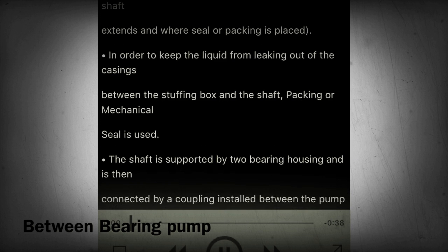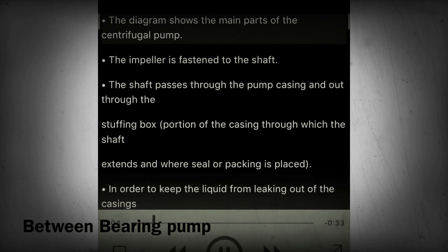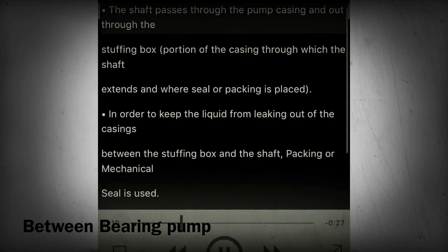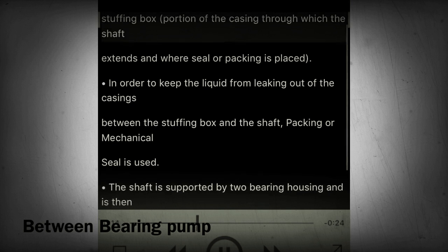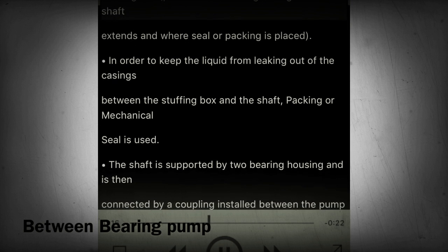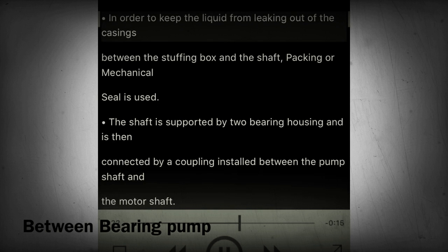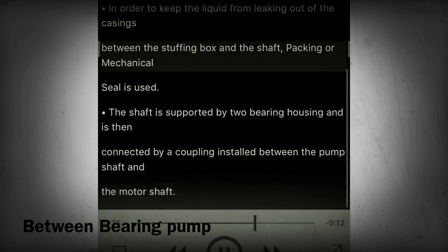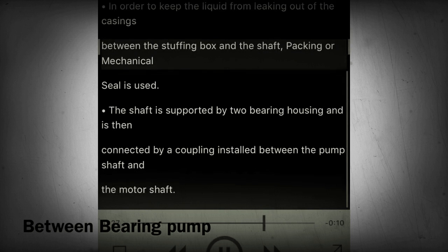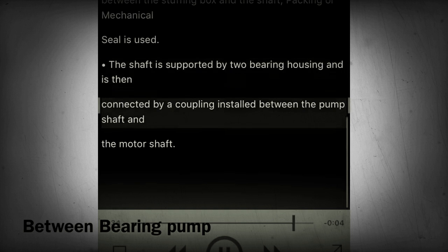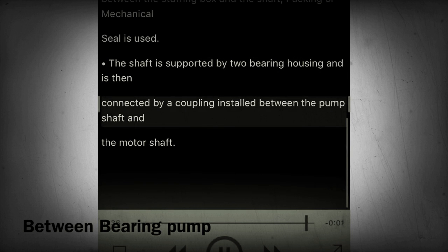Sections 18-19 - Nomenclature and Description. The diagram shows the main parts of the centrifugal pump. The impeller is fastened to the shaft. The shaft passes through the pump casing and out through the stuffing box — the portion of the casing through which the shaft extends, where a seal or packing is placed in order to keep the liquid from leaking out of the casing. Packing or mechanical seal is used. The shaft is supported by two bearing housings and is connected by a coupling installed between the pump shaft and the motor shaft.